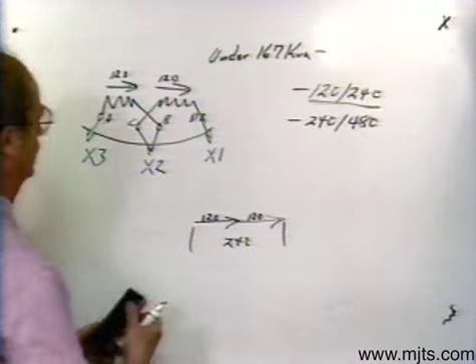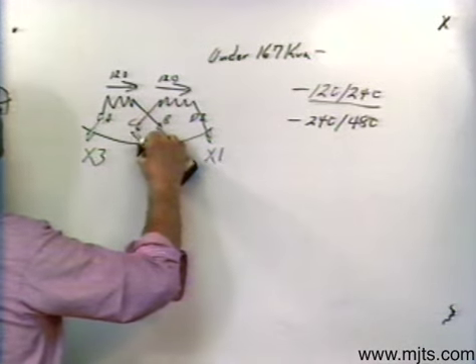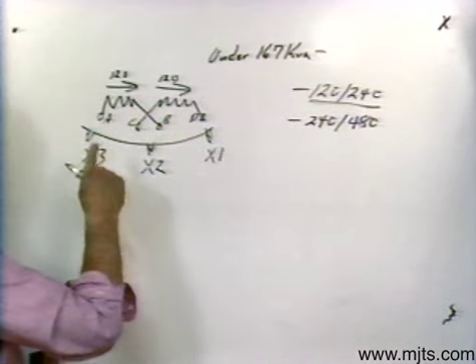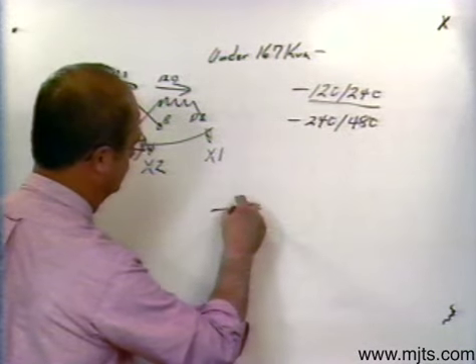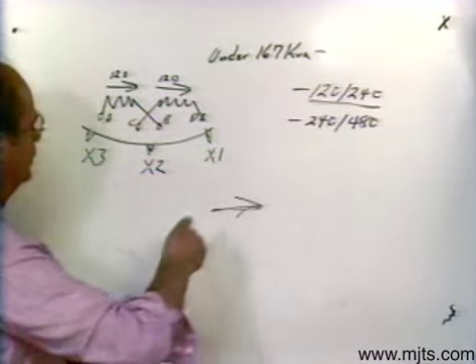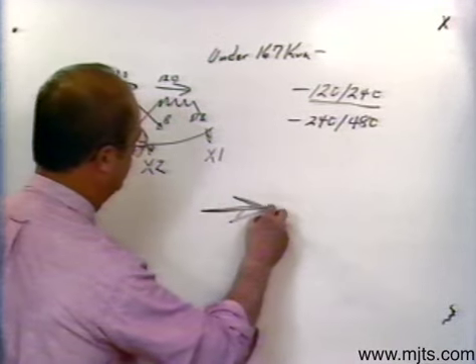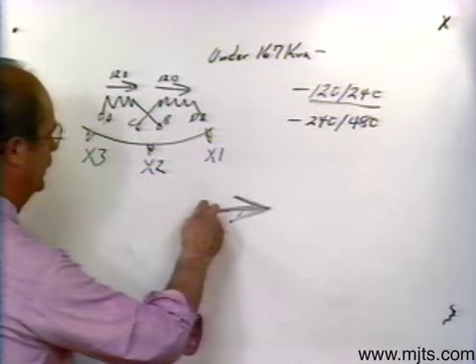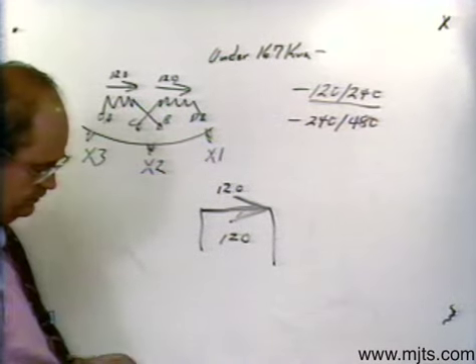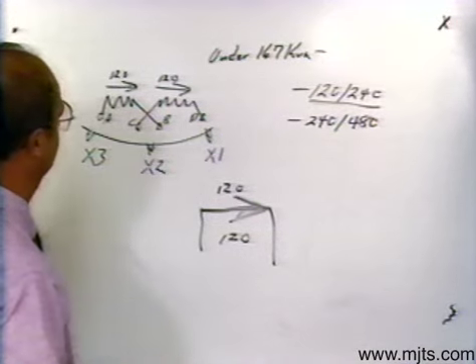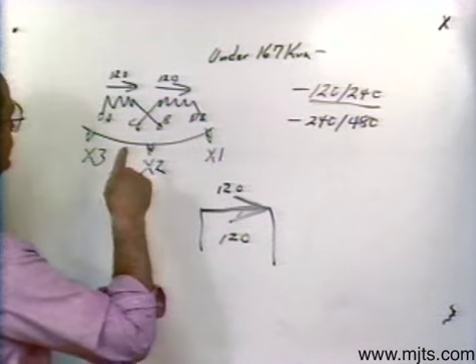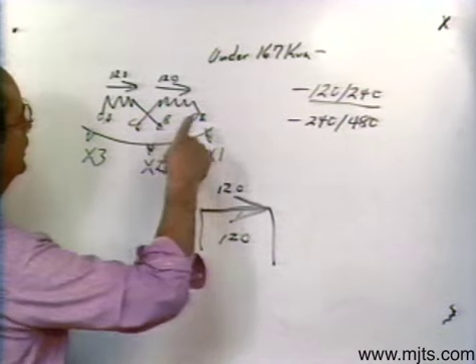Now let's say that instead of 240 volts I want 120 only. If I have a voltage vector of 120 volts, what I would do is put one vector right on top of the other — tie tail to tail and head to head. The voltage value I would get out of that would be 120 volts. To connect this transformer for 120 volts only, you have to make sure you use only X2 and X1.